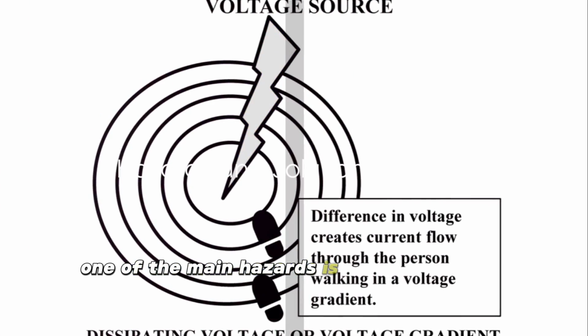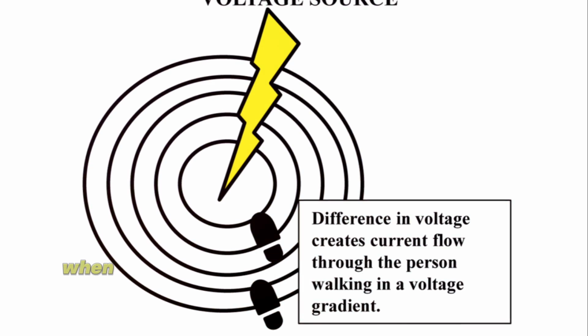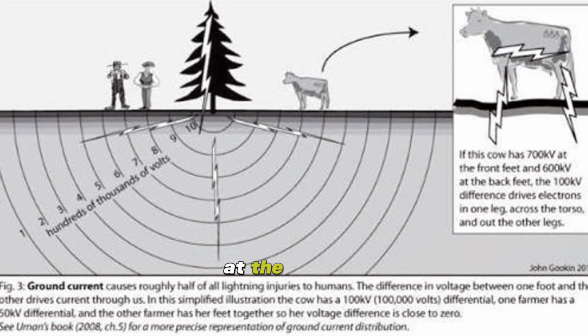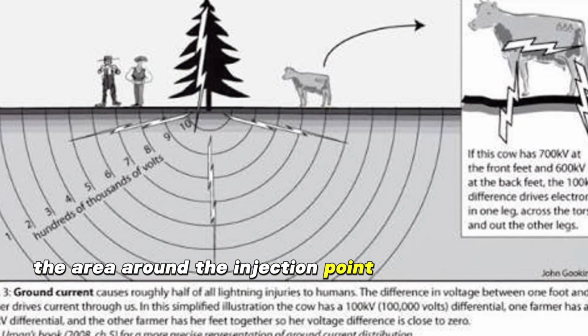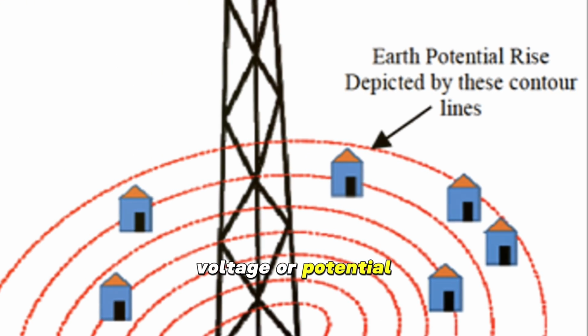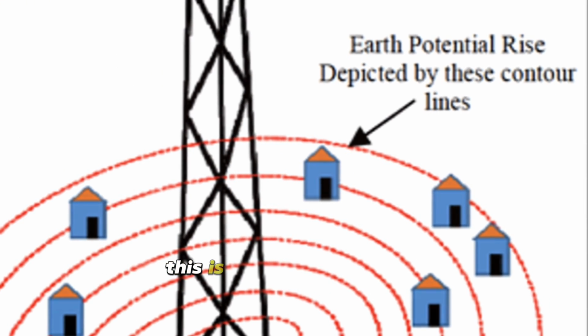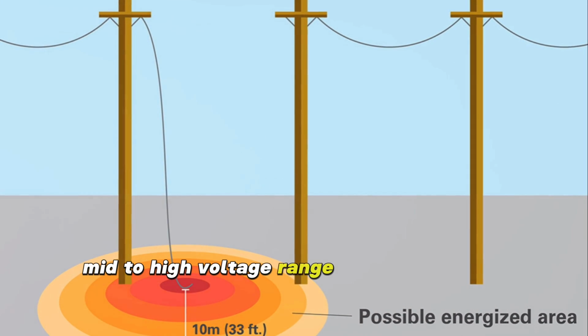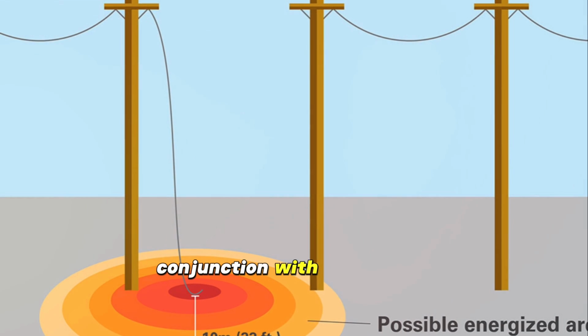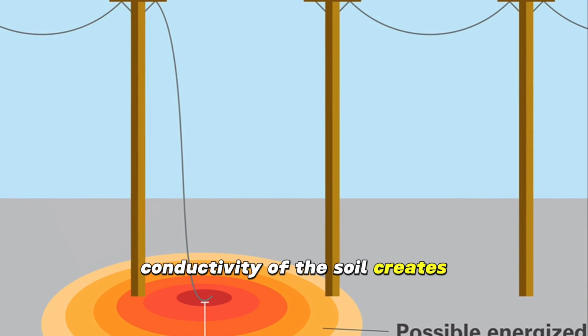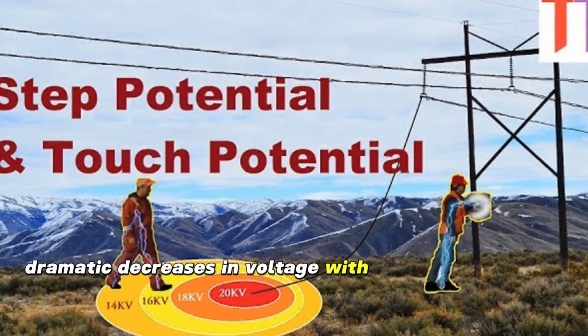One of the main hazards is the risk of earth voltage potential rise. When large currents are injected into the earth at the surface, the area around the injection point may rise to a high voltage compared to points around the transmitter. This is because the typical mid to high voltage ranges used, in conjunction with the limited conductivity of the soil, creates dramatic decreases in voltage with distance.